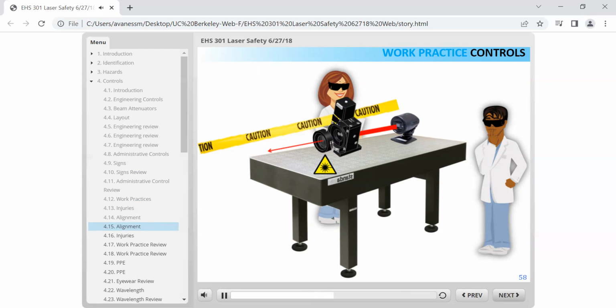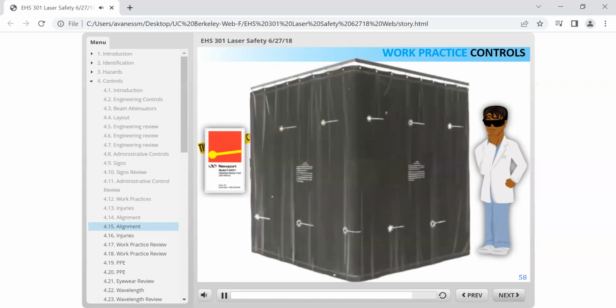Simulate the beam path using lower power visible lasers. Terminate any stray or unused beams. Use beam shutters to block high power beams anytime they aren't needed. Terminate the beam at the end of its useful path. Eliminate all beams and reflections prior to high power operation. View invisible beams with IR or UV cards or sensor cards, taking care to avoid specular reflections off some of these materials. Do not look directly at the beam. You can prevent intentional intrabeam viewing with the eye by using cameras or fluorescent devices to view the beam.